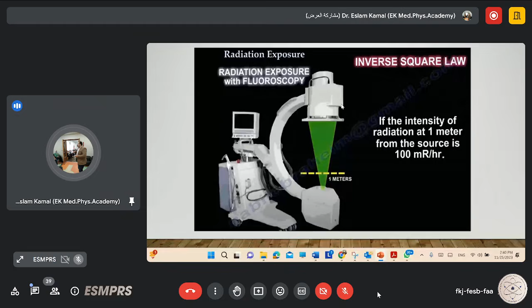As you can see here, this is our C-arm machine, or fluoroscopic machine, and we have the X-ray tube and our image intensifier, or detector. Now if you are at 1 meter, you get exposed to 100 milliroentgen per hour. If you double the distance, you get exposed to 25 milliroentgen per hour. So as per the inverse square law, which is very important for anyone, distance is a significant factor to reduce the radiation intensity. So I advise everyone to keep distance away from any radiation source. The distance is very significant to reduce the radiation exposure.